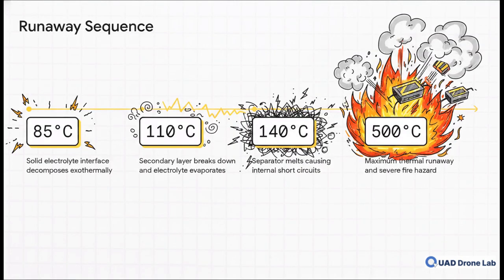And that heat triggers a terrifying chain reaction. Watch how fast this escalates. At 85 degrees Celsius, the solid electrolyte interface breaks down and starts generating its own heat. By 140 degrees, the internal separator melts, causing massive short circuits, and suddenly you're rocketing up to 500 degrees Celsius in full-blown catastrophic thermal runaway.